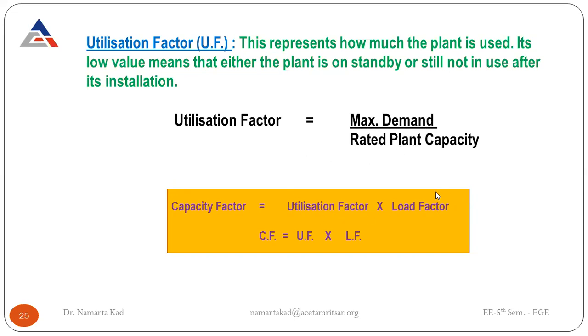So the relation between the capacity factor, utilization factor and load factor is that the capacity factor is equal to the utilization factor into the load factor. Just note it down. It's a very important formula. Capacity factor is equal to utilization factor into load factor.